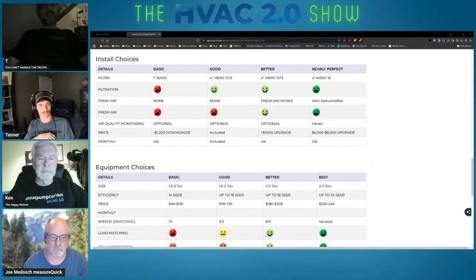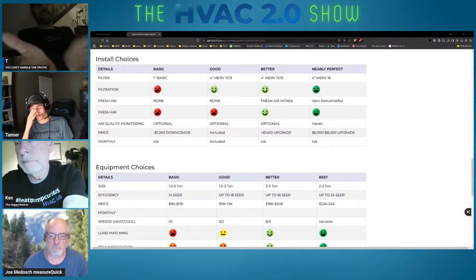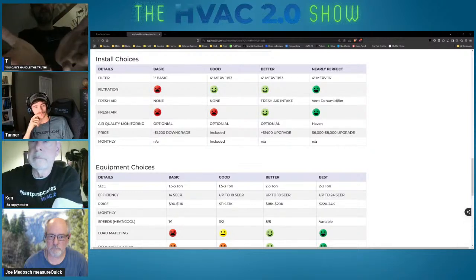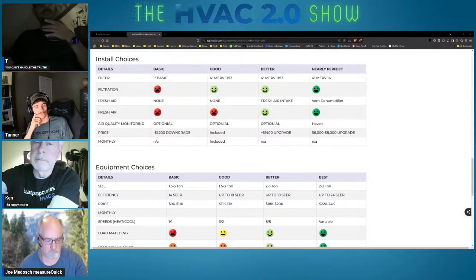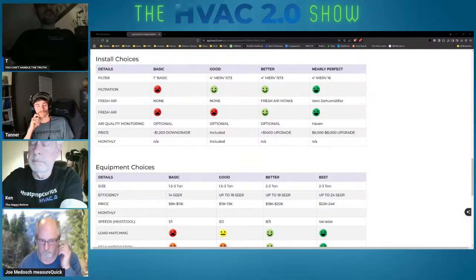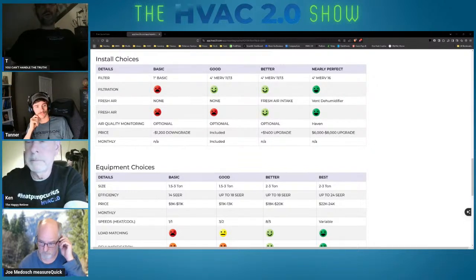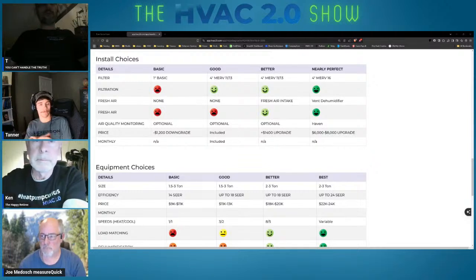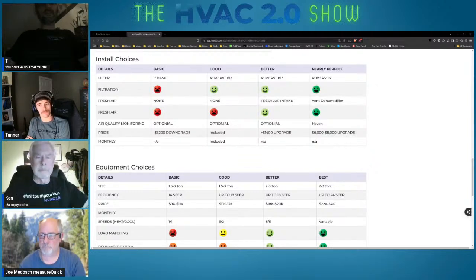With MeasureQuick, you can show the homeowner something like: you've been comfortable with this 4-ton unit that's only been delivering 2.5 tons because you only had 2.5 tons of ductwork. As you can see from this report, here's the capacity you've been getting. Unfortunately, the new equipment is not going to work on the existing ductwork — you can't buy 4 tons of equipment that'll deliver 2.5 tons in single stage.